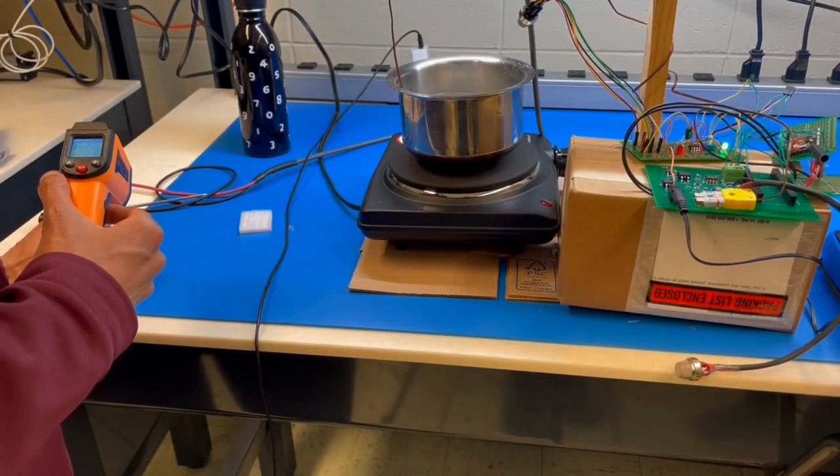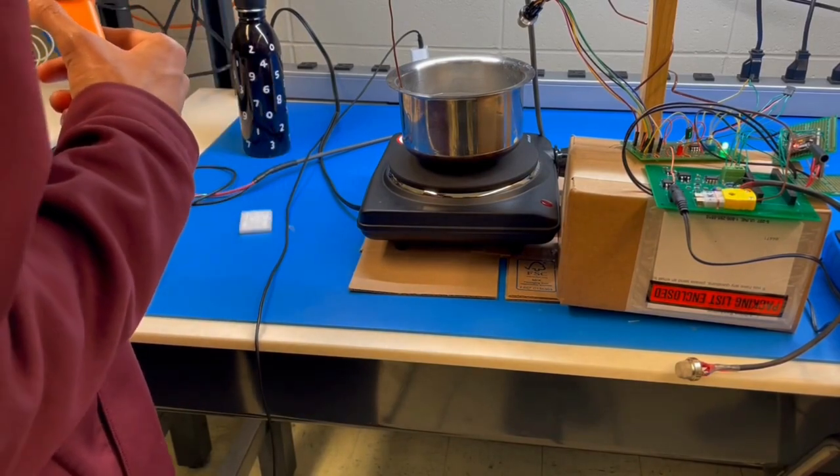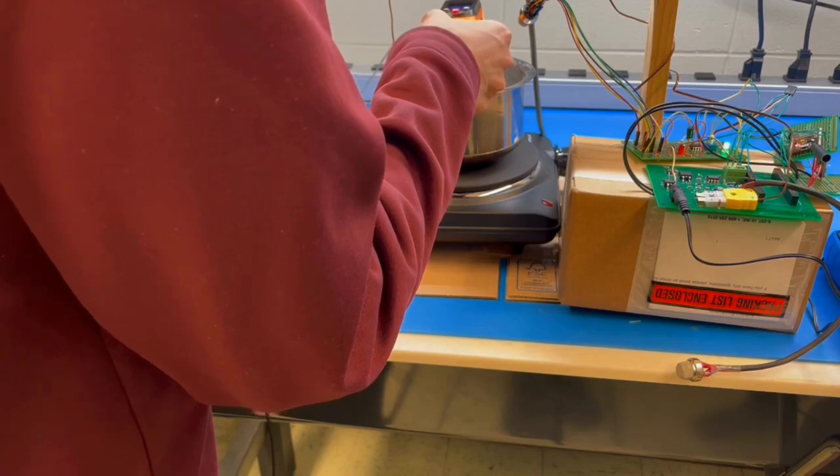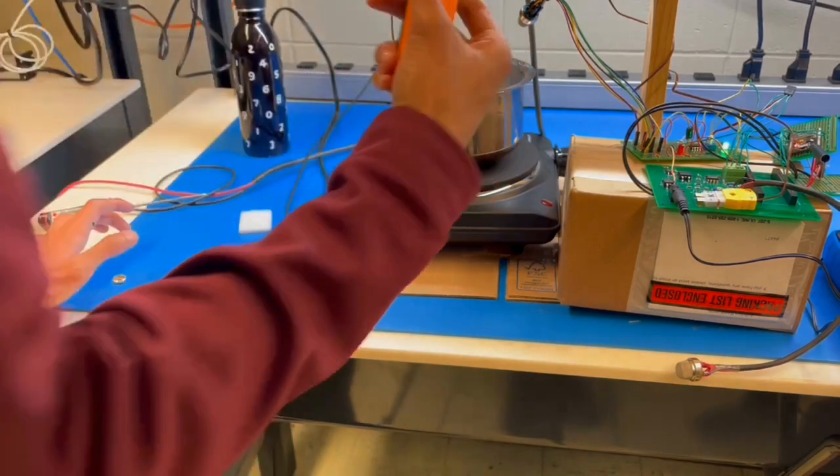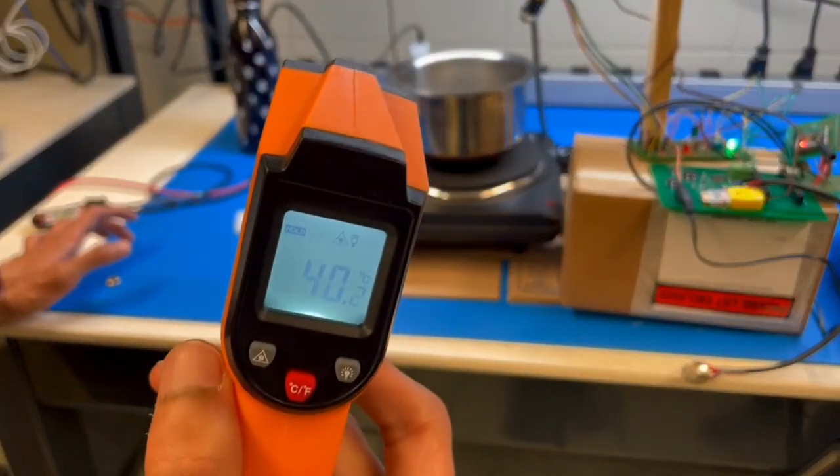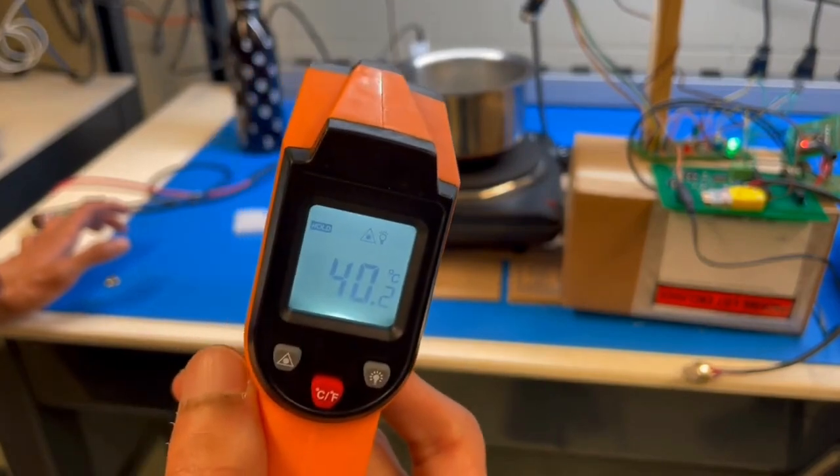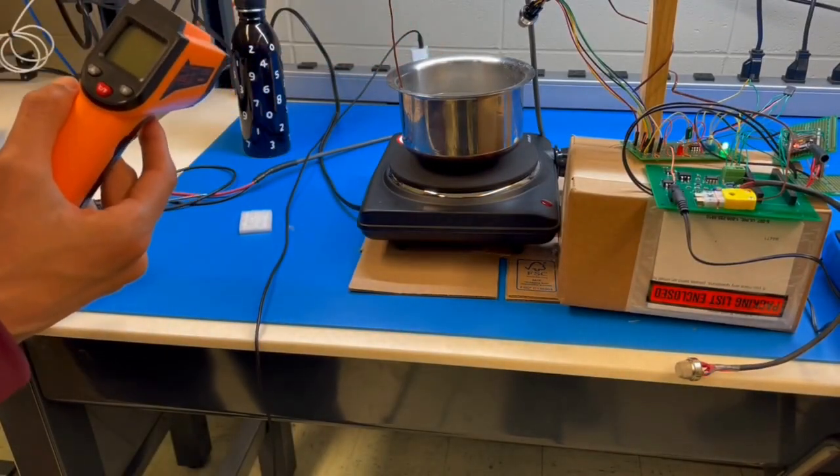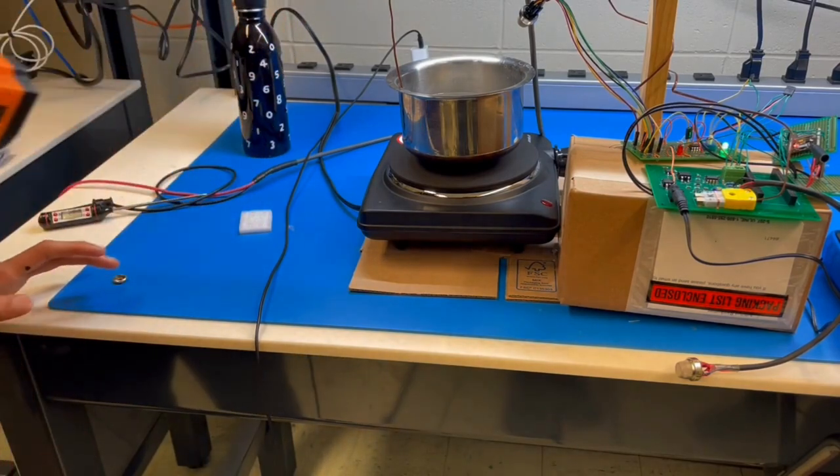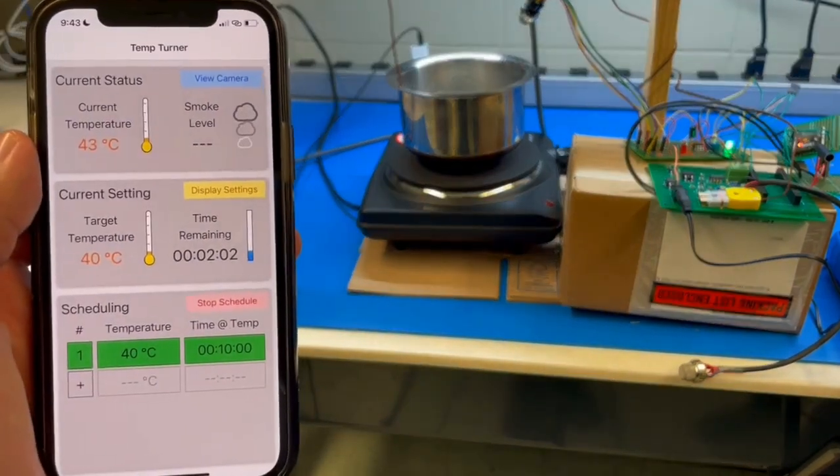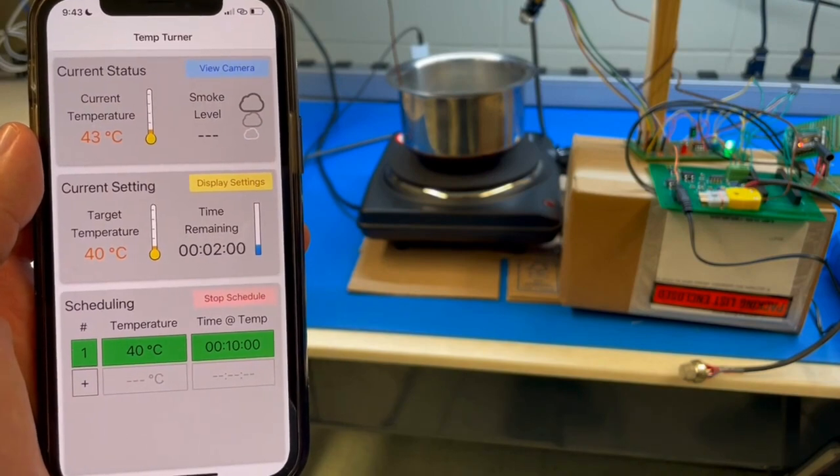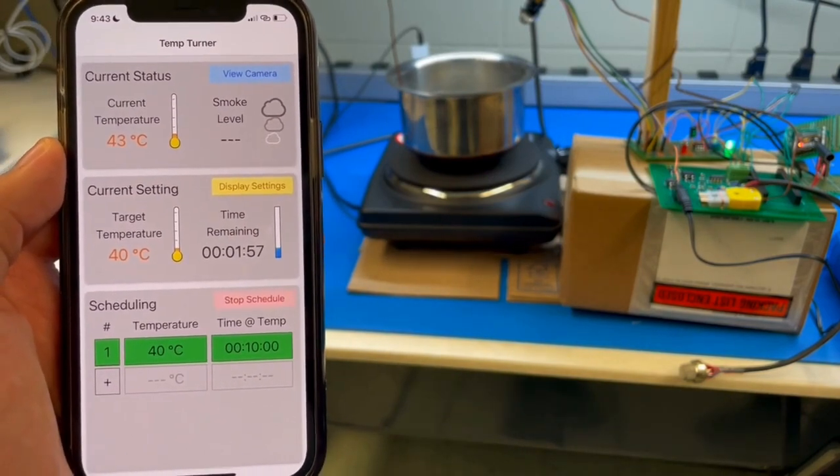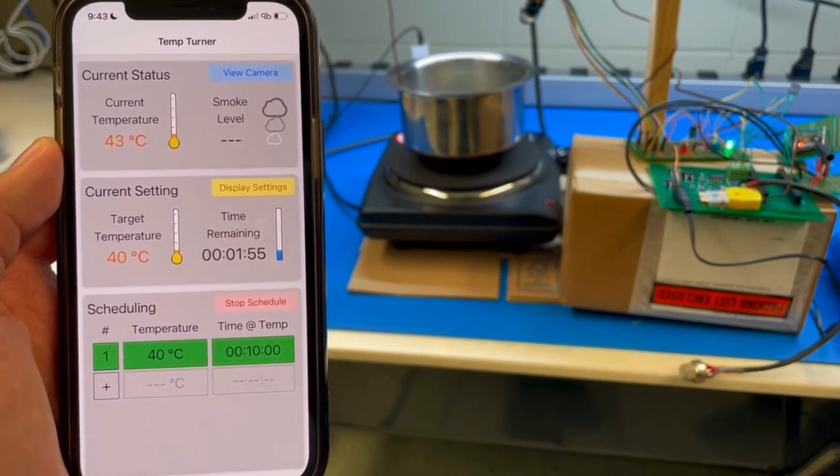We've reached the last scheduled temperature and the water is almost at 40 degrees Celsius. The IR thermometer shows a reading of about 40.2 degrees Celsius. The smoke detector, as seen here, continues to remain off. Let's now see what the app shows. The app also shows a similar value of about 43 degrees Celsius, and the red LED on the app also continues to be off.